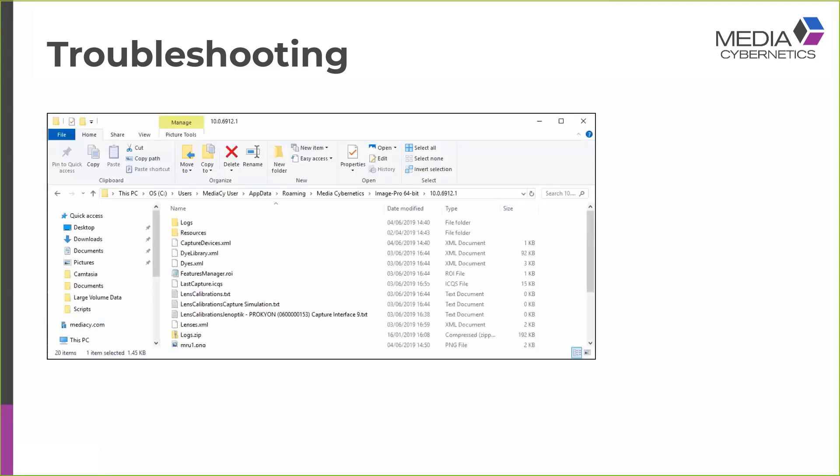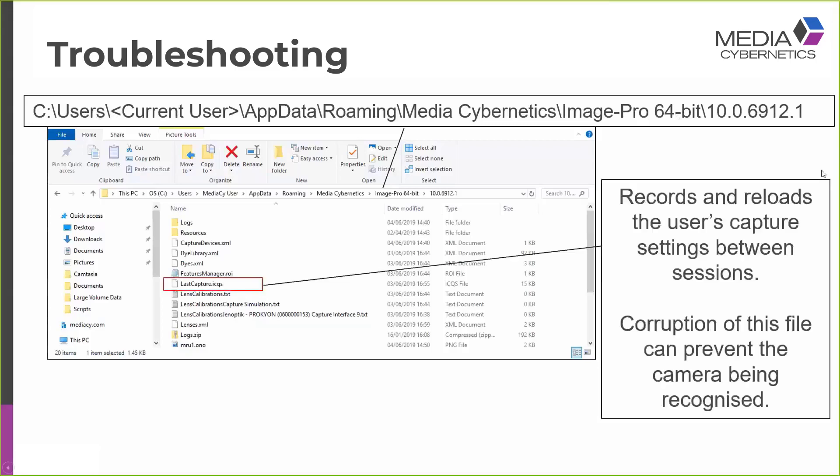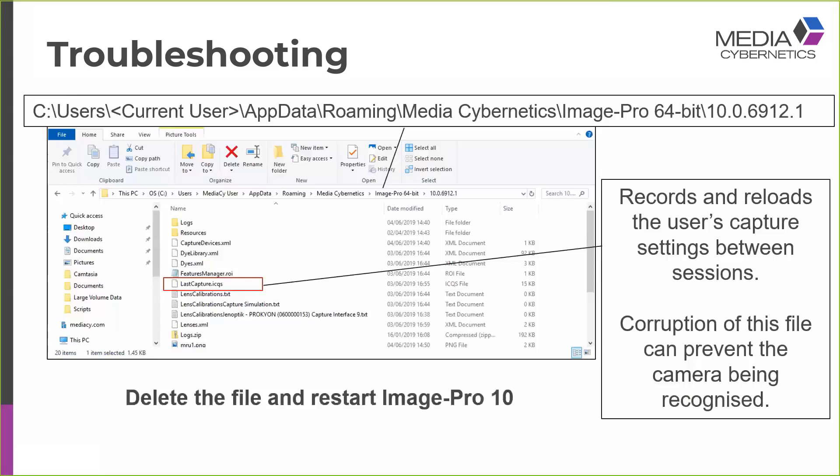Another troubleshooting step you can make is to navigate to a file that you'll find tucked away in the users folder. So if you go to the users, check in the current users folder. Look for AppData, Roaming, Media Cybernetics, Image Pro 64-bit, and then you'll find a folder for the Image Pro version you're working with. In there, there's a file called LastCapture.icqs. And this records and reloads the user's capture settings between sessions. Corruption of this file can prevent the camera being recognized and loaded. The solution is to delete this file and restart Image Pro 10.